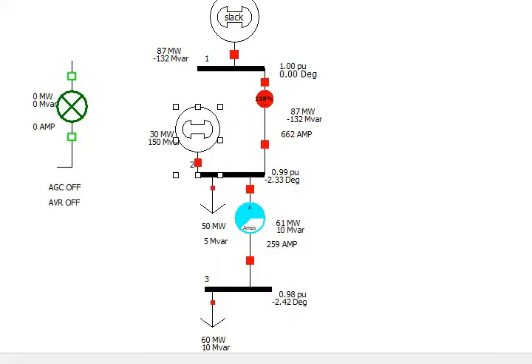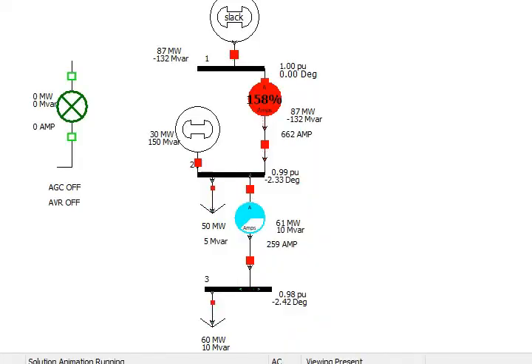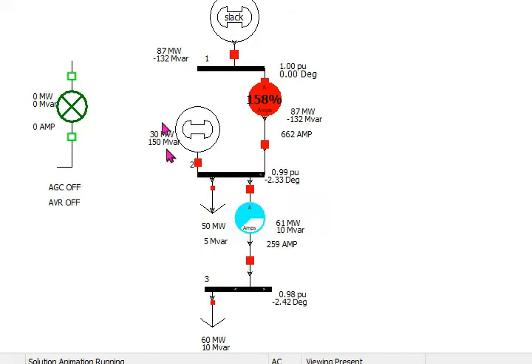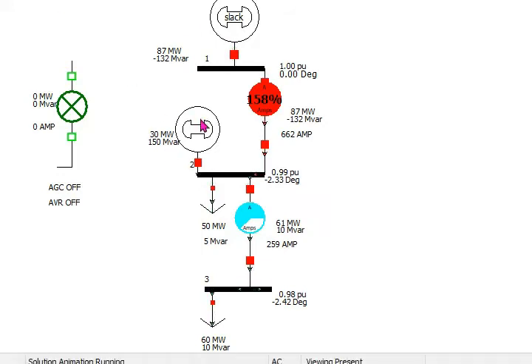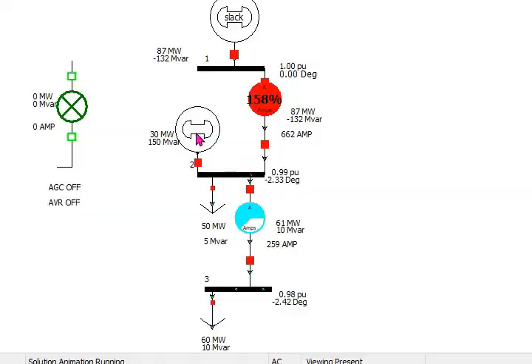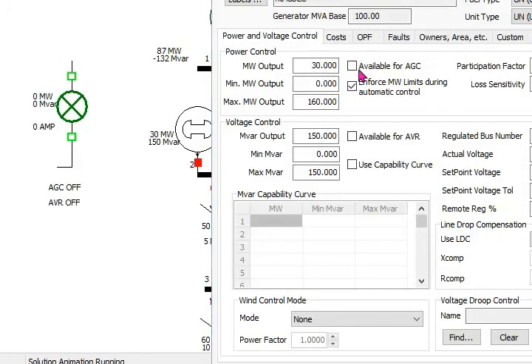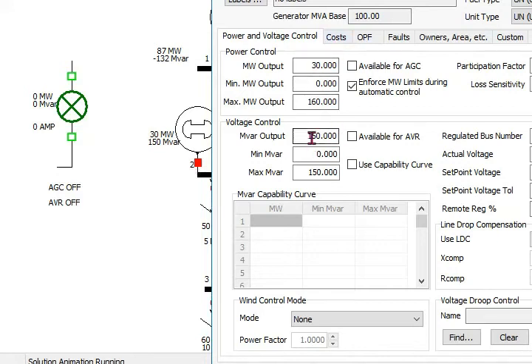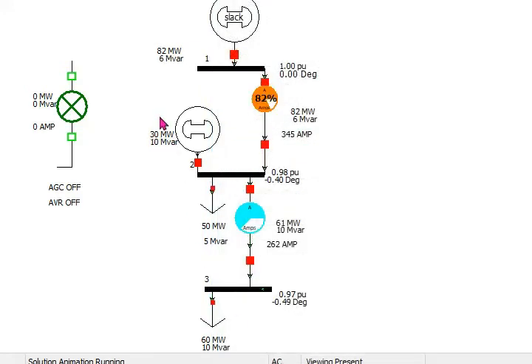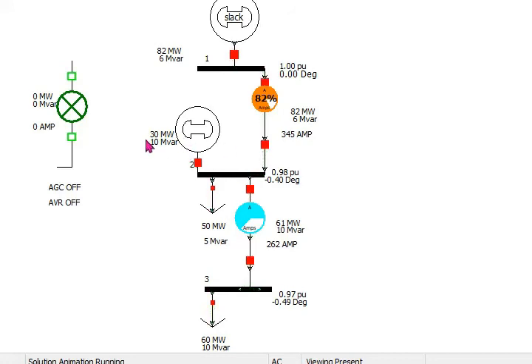So again we have unselected, but first we have to reset and then we have to reduce the limits. As the limits there is 150 megavar, this is selected by the AVR. Double click on it, and in the megavar control output, reduce it here to 10 megavar and then click OK. And then run it, so it will be in the previous state. The voltage at this one is now 0.98.